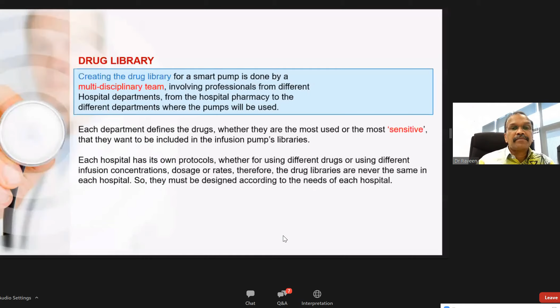Medication errors have serious implications. I'm repeating this again, to both the patient as well as the healthcare system. It can compromise patient safety, and because of the medication error, healthcare costs can go up. So what are the factors contributing to a medication error with an infusion pump or a smart pump? The programming. This is incorrect entry of a setting or a value into an infusion pump. The provider may have entered incorrect information for a range of reasons, such as keying in the incorrect patient weight or the incorrect units. So instead of mils per hour, puts milligrams per kg per hour.